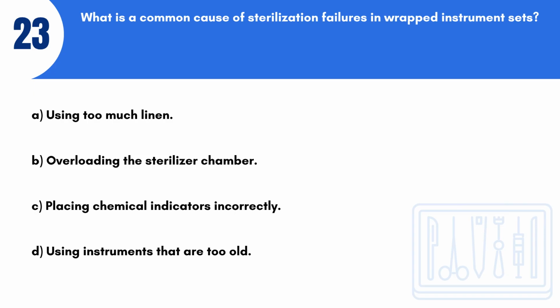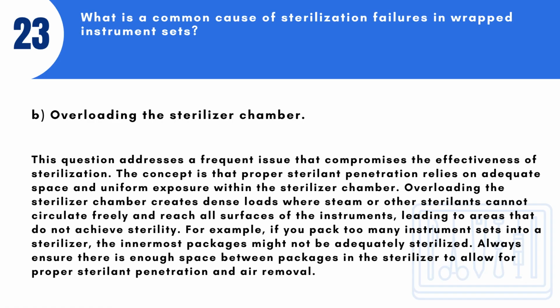Question 23. What is a common cause of sterilization failures in wrapped instrument sets? A. Using too much linen. B. Overloading the sterilizer chamber. C. Placing chemical indicators incorrectly. D. Using instruments that are too old. Answer: B. Overloading the sterilizer chamber.